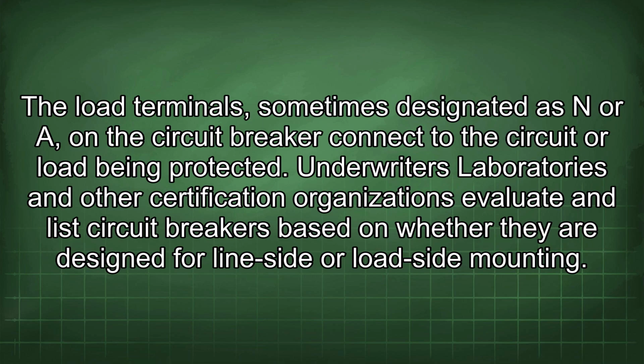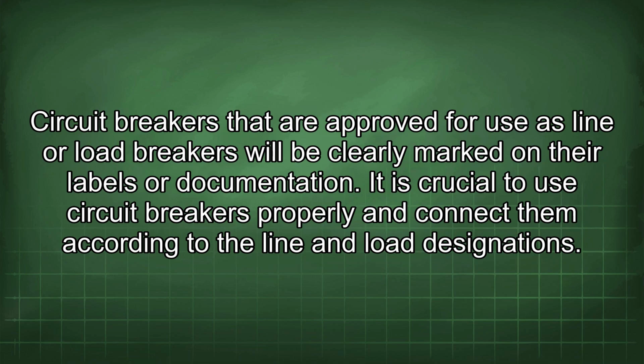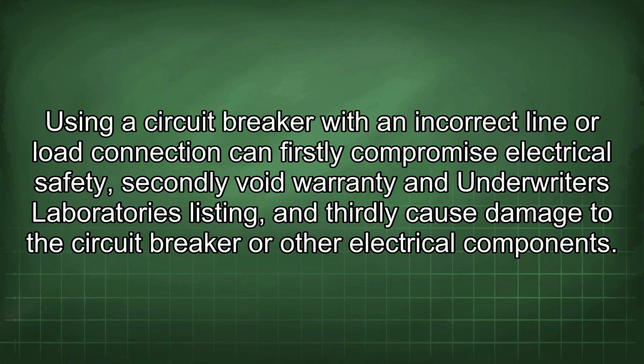Underwriters' Laboratories and other certification organizations evaluate and list circuit breakers based on whether they are designed for line-side or load-side mounting. Circuit breakers that are approved for use as line or load breakers will be clearly marked on their labels or documentation. It is crucial to use circuit breakers properly and connect them according to the line and load designations. Using a circuit breaker with an incorrect line or load connection can firstly compromise electrical safety, secondly void warranty and Underwriters' Laboratories listing, and thirdly cause damage to the circuit breaker or other electrical components.